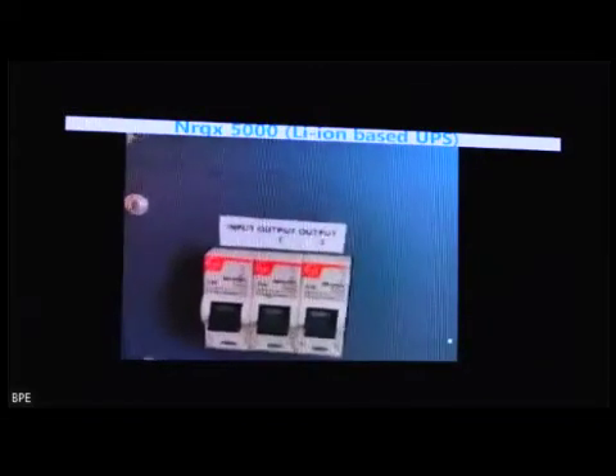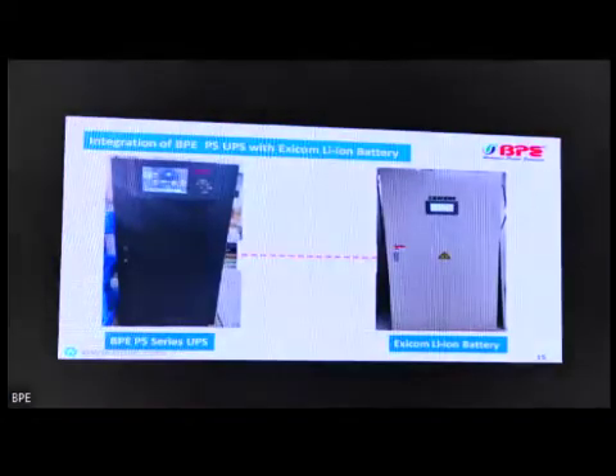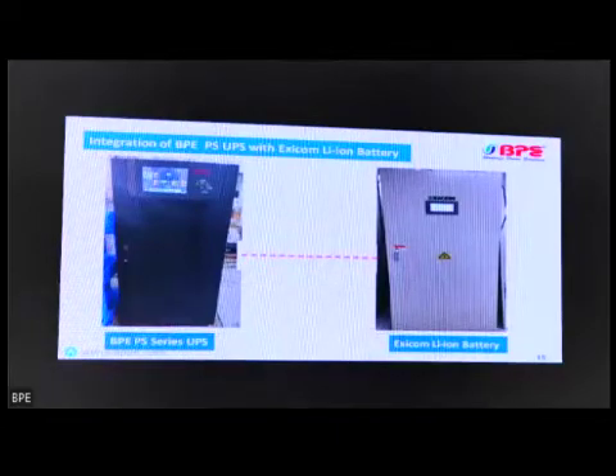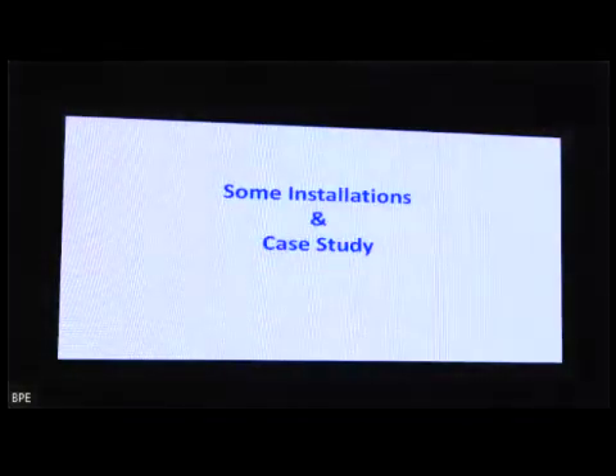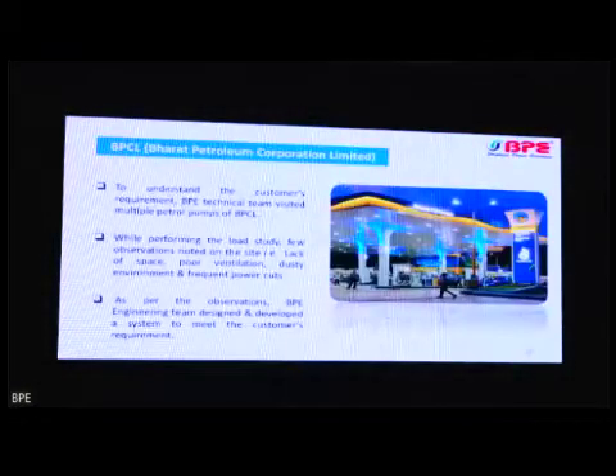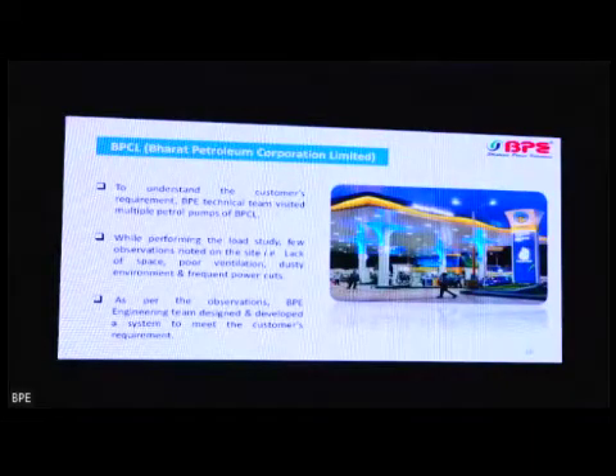Manual bypass switch is there. In case of any issue, we can bypass the UPS system. All the Indian type of sockets are available there. There is a tray on the bottom of the UPS, so you can slide the UPS without any issue. And the rear panel is also screw-less. It is just pressed to fit. Very easy for the servicing point of view. We have also integrated our PS series UPS with Exicom lithium-ion batteries for higher ratings.